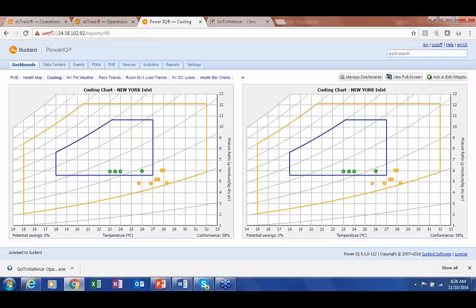I'll start with a patented cooling chart that we have. This patented cooling chart allows for the display of data centers with 50 racks, for example, or data centers with 10,000 racks. You can easily display all the environmental sensor information on a psychrometric chart within the ASHRAE envelope that defines the proper operating conditions for air coming into the inlet side of a cabinet and cooling IT equipment. Here in blue is the ASHRAE defined range, and any cabinets within that range show up as green; you can mouse over and see the temperature, humidity, and location.